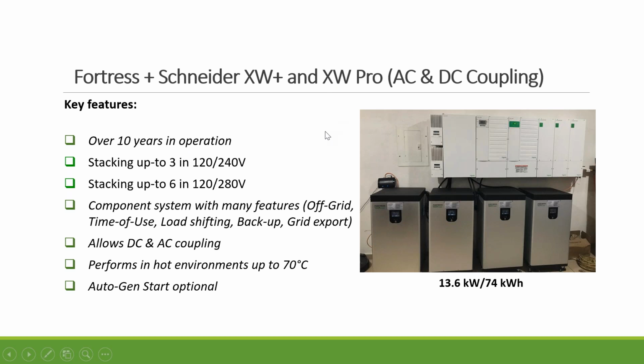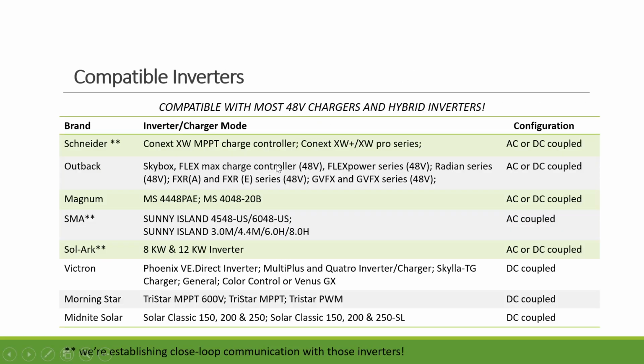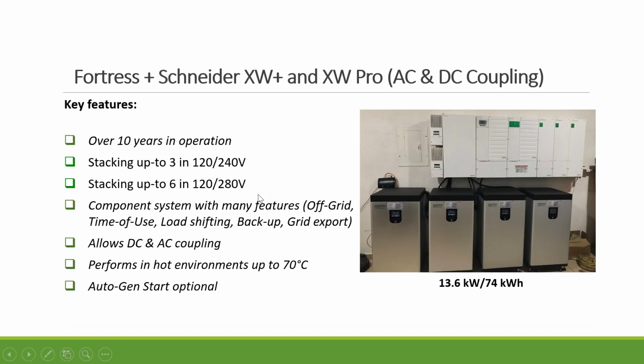So a lot of you may have already used Schneider inverters in the past. They have the XW Plus and XW Pro. Those are the main two products now on the market. We like that solution a lot. It's a very robust system. You can use it for 3-phase. Actually, I think it's for 4 units instead of 3 units, sorry for that. And you can also use it in commercial applications. You can stack multiple of them on each phase, 1, 2, or 3, and get into a bigger system. It supports off-grid, time of use, load shifting, backup, and grid export.